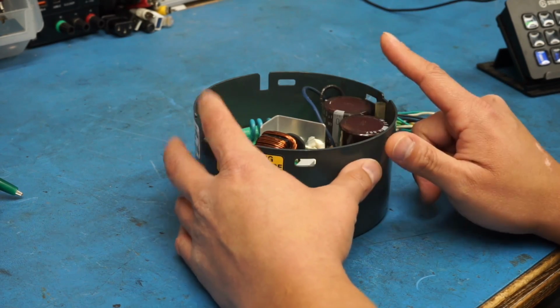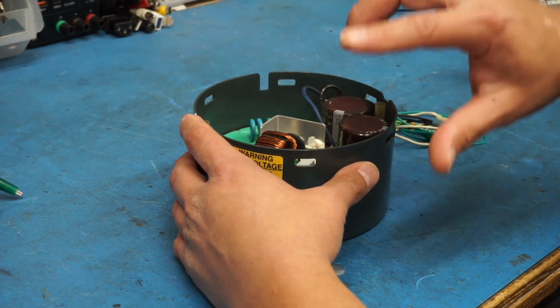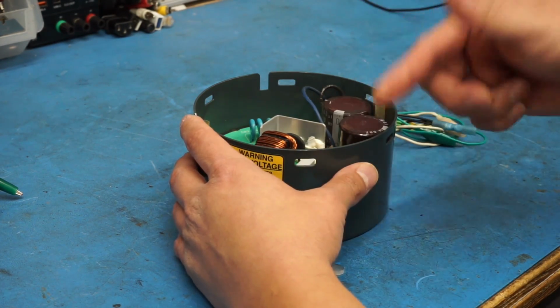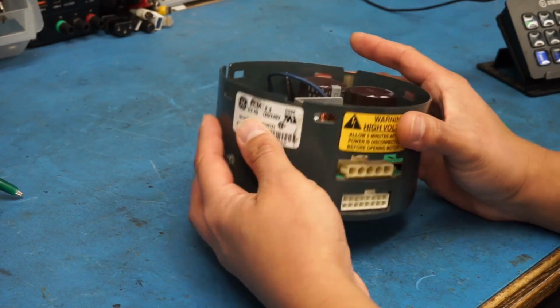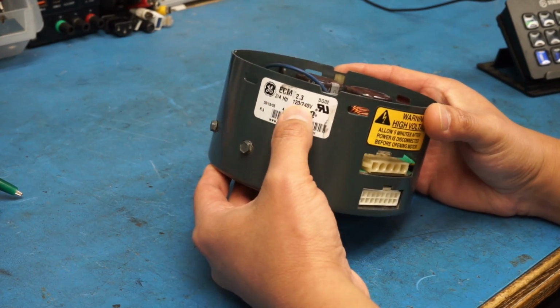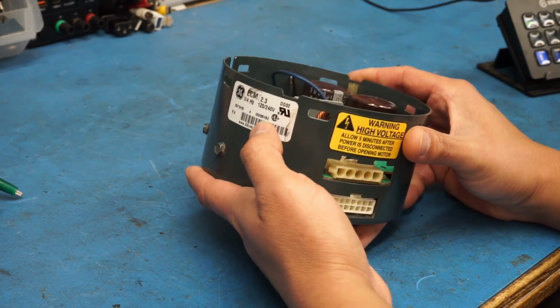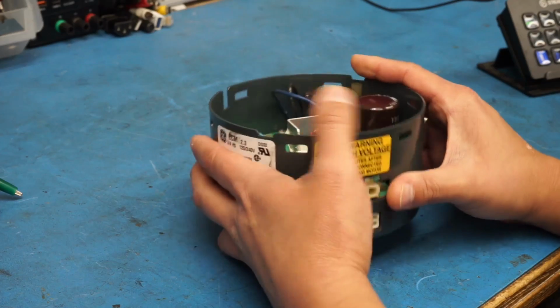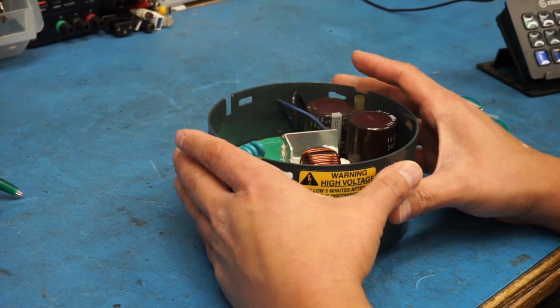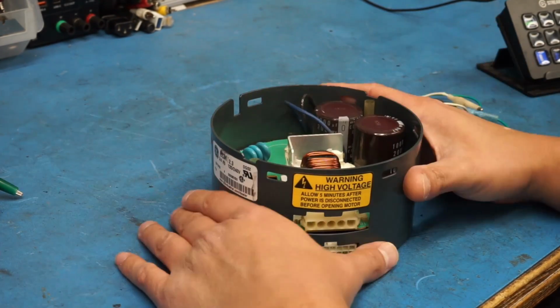One thing you need to know about your motor is whether the blower rotates clockwise or counterclockwise. Looking at the blower from the shaft end on this unit, the motor rotates clockwise. When I looked for a replacement unit, I looked for one with the same model number and clockwise as its rotation direction. The one I bought said CWLE on the description, and that's where I messed up.